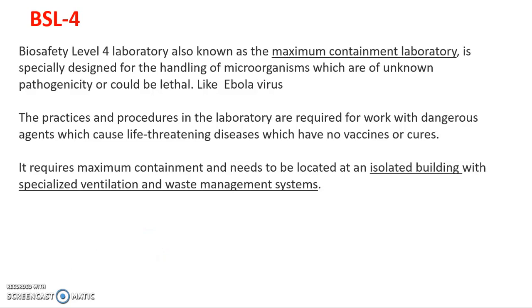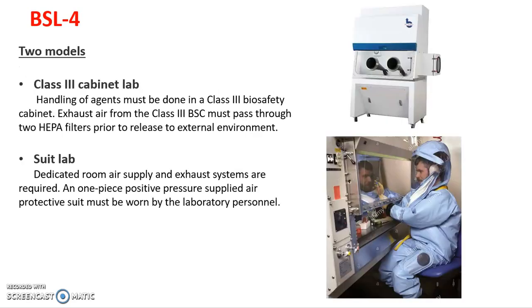Biosafety level four (BSL-4) is the maximum containment laboratory. Persons work with microorganisms that are very infectious, can cause disease for which no vaccine or cure is available, or are of unknown infectivity or pathogenicity — and can be lethal. BSL-4 laboratories are built in isolated buildings with specialized ventilation and waste management systems. Even the air released to the environment is first properly filtered. There are two models: the Class III cabinet model and the suit lab model.